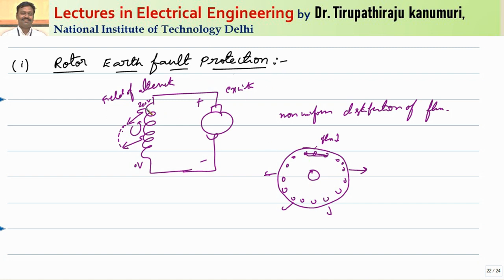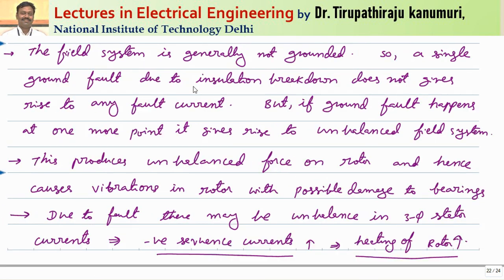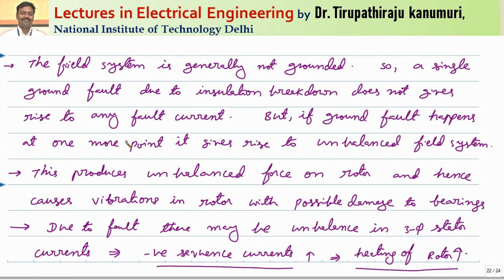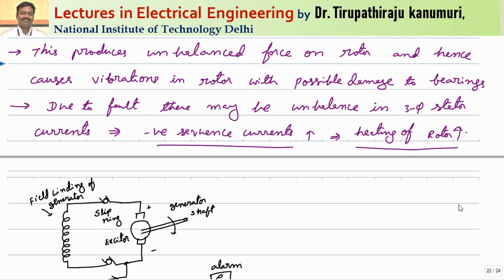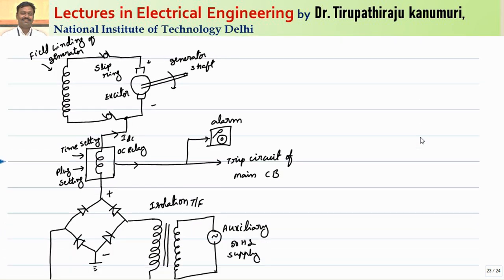Whenever a single ground fault happens between the rotor field poles and the rotor core, it should immediately be disconnected so that it will not develop into another fault. A single ground fault due to insulation breakdown does not give rise to any fault current. But if a ground fault happens at a second point it gives rise to an unbalanced field system. This produces unbalanced force on the rotor and causes vibrations with possible bearing damage. Due to the fault, negative sequence currents will heat both stator and rotor, so it should be protected at an early stage.